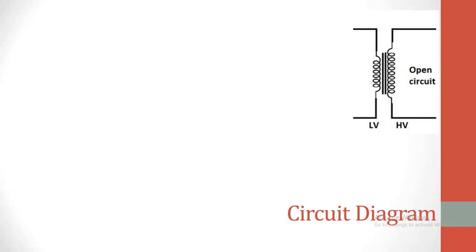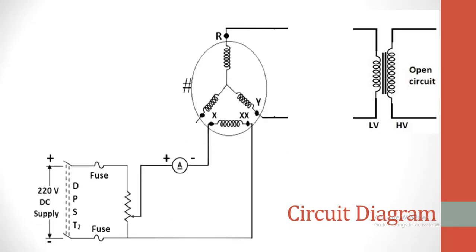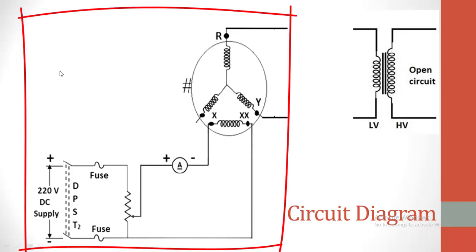This is the transformer circuit alone. The secondary is kept open. On this transformer, we should conduct an experiment to separate the losses. This experiment should be conducted at variable voltage and frequency by maintaining the ratio of V/F constant. Hence, we are using the synchronous generator.